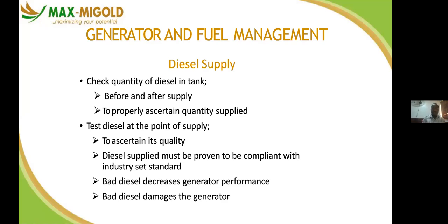We have the density test, the capillary test of the density. There's a standard set for that. You have the clarity test, to see if the color of the diesel is okay. The water test, which is done with litmus, and so on. So there are various things that can tell you whether this diesel is clean or not, okay or not. So you ensure that is done. You can't be too busy to do it.